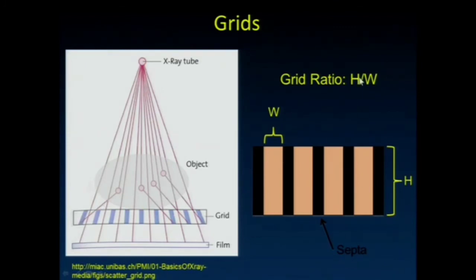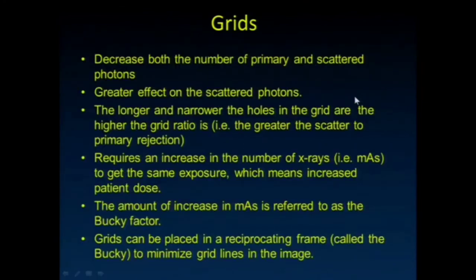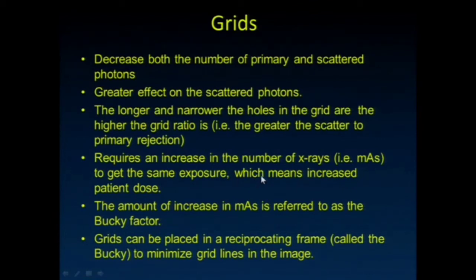There's that grid ratio — the height of the holes divided by the width of the holes. Grids decrease both primary and scatter, with a greater effect on scatter. The longer and narrower the holes are, the more rejection they give. Grids always require an increase in the number of X-rays because the number of X-rays hitting the detector goes down with the grid, so you've got to provide an increased dose to that patient. The amount of increase in mAs required is referred to as the Bucky factor, and that represents an increased dose to the patient.